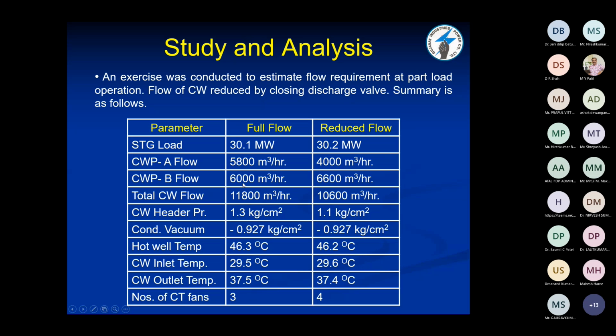Now CW pump B, that was running at 6,000 meter cube, comes to 6,600 because by reducing the other flow, this has increased. Now total cooling water flow is 11,800 and this is 10,600. Cooling water header, earlier it was 1.3 kg, now it is 1.1 kg. Condenser vacuum also remains the same. There is no effect on the condenser vacuum. Hot well temperature also remains the same. Cooling water inlet temperature remains the same. Outlet temperature remains the same. And number of CT fans, earlier it was 3, now it has become 4.